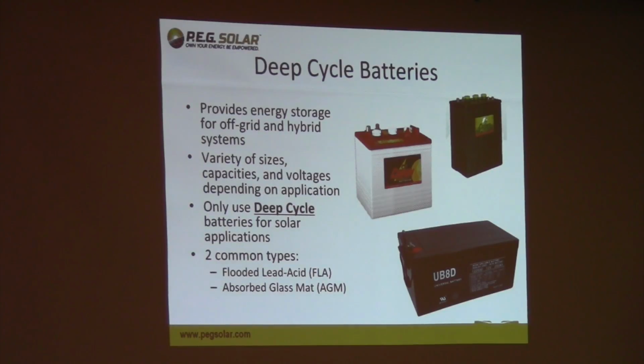AGM batteries also give you slightly better charging and discharging efficiency, so more of what you charge in, you get back out. However, they're not as durable as the flooded battery, so they won't last as long. Typically, for standby applications where the battery is only used in an emergency, maintenance-free sealed AGM batteries are the way to go - nothing to think about, no real headache, no extra chores for the system owner. For people who are 100% off the grid, they typically go with the traditional flooded battery. If you're 100% off-grid, you're already used to doing a lot of chores and knowing how to take care of yourself, so that just becomes part of the routine.